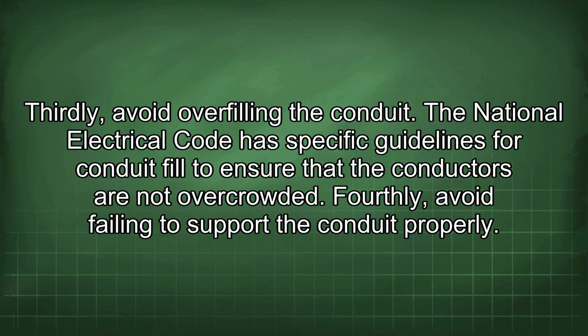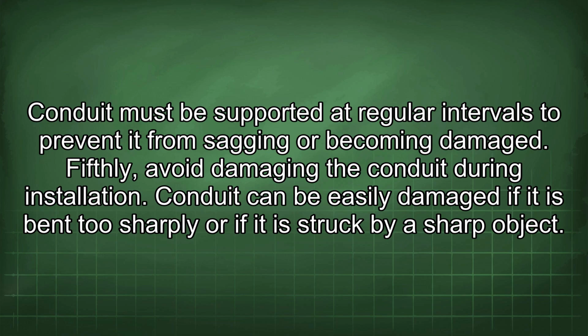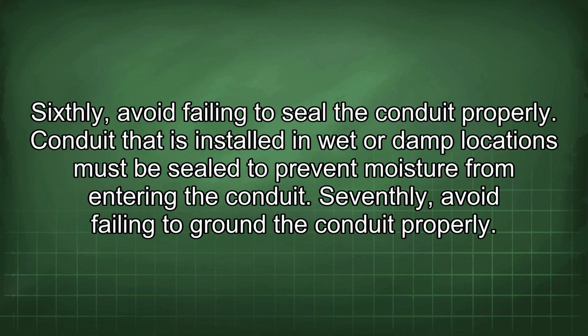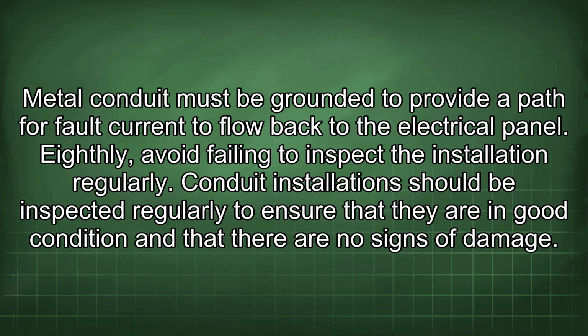Fourthly, avoid failing to support the conduit properly. Conduit must be supported at regular intervals to prevent it from sagging or becoming damaged. Fifthly, avoid damaging the conduit during installation. Conduit can be easily damaged if it is bent too sharply or if it is struck by a sharp object. Sixthly, avoid failing to seal the conduit properly. Conduit that is installed in wet or damp locations must be sealed to prevent moisture from entering the conduit. Seventhly, avoid failing to ground the conduit properly. Metal conduit must be grounded to provide a path for fault current to flow back to the electrical panel.